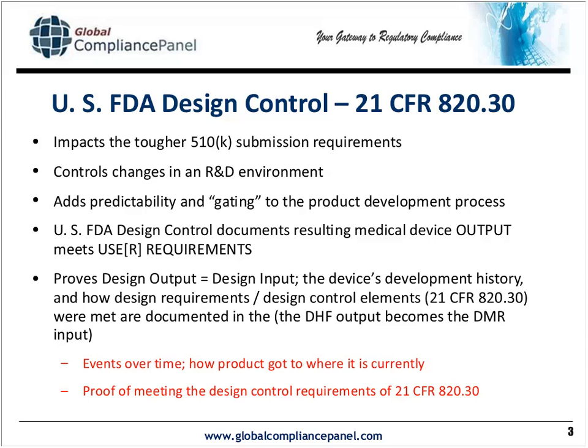But now, the design history file talks about the events over time in developing that product. In other words, the history of how the product got from a start date in R&D to where it is currently, or generally to where it was in design transfer, depending on which of the two models you choose to use as a company. And then the design history file shows the proof of how design control requirements of 21 CFR 820.30 were in fact met by means of documentation.